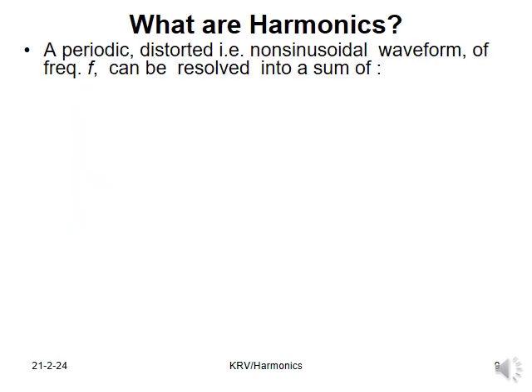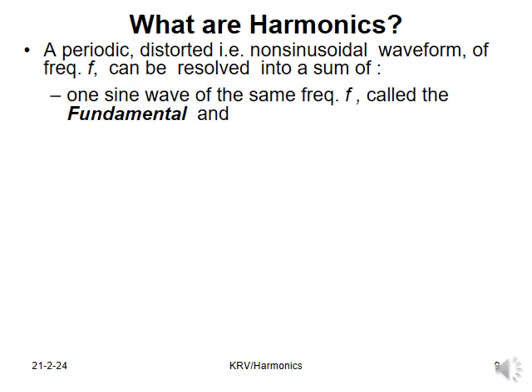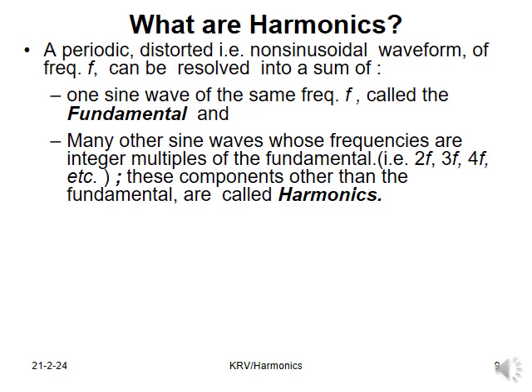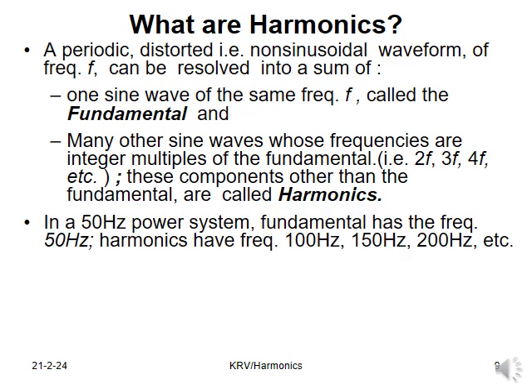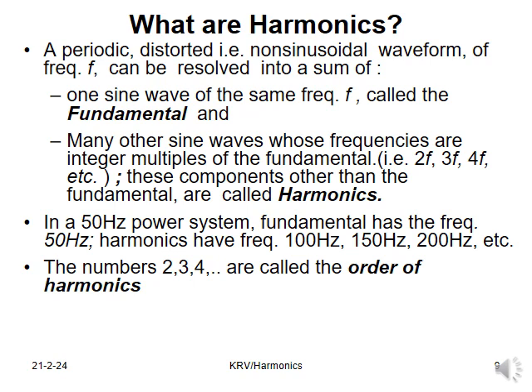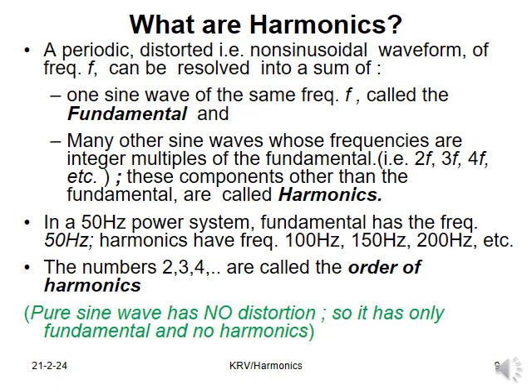So, what are harmonics? A periodic, distorted, that is non-sinusoidal waveform of frequency f can be resolved into a sum of one sine wave of the same frequency f called the fundamental and many other sine waves whose frequencies are integer multiples of the fundamental, that is 2f, 3f, 4f, etc. These components other than the fundamental are called harmonics. In a 50 Hz power system, the fundamental has the frequency of 50 Hz, and harmonics have frequencies of 100 Hz, 150 Hz, 200 Hz, etc. Theoretically, they can go to a large number, up to infinity. The numbers 2, 3, 4 are called the order of harmonics. A pure sine wave has no distortion, so it has only the fundamental and no harmonic.